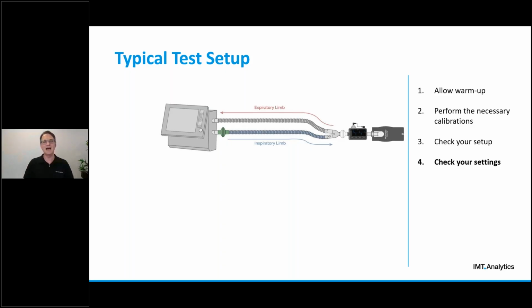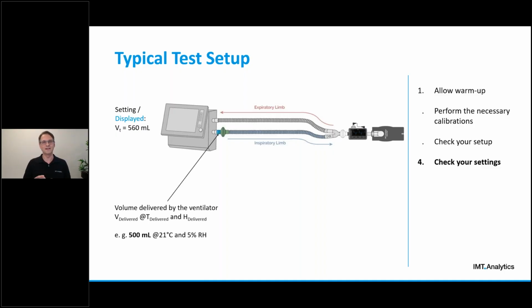And in such a situation, it can easily happen that you set a tidal volume of 560 milliliters on your ventilator, but you only measure a VTI of 500 milliliters on your gas flow analyzer. So how can that be? Well, assuming that the ventilator setting is using the gas standard BTPS, this means, as we've learned earlier, that it's going to underdeliver in volume because it considers an increase of the volume in the circuit system in a real patient situation, as we have a humidifier and a heated inspiratory limb, and that volume is going to increase while it travels along the circuit system until it reaches the patient.